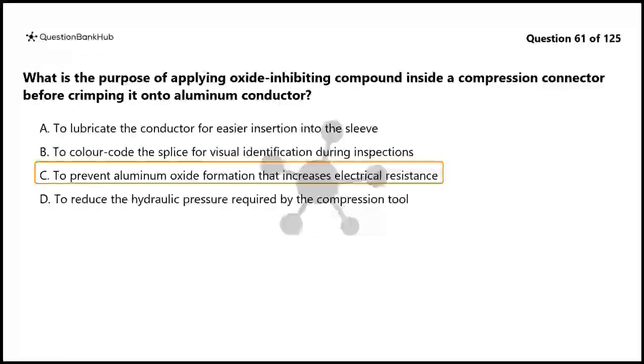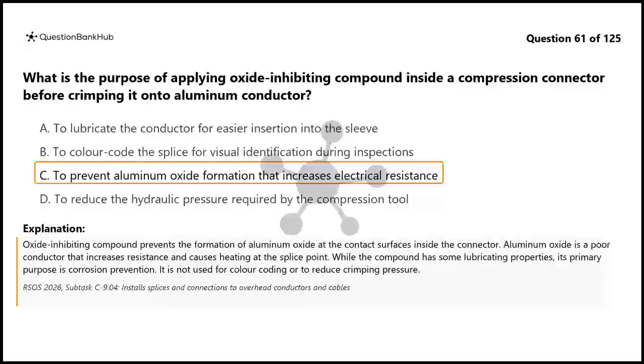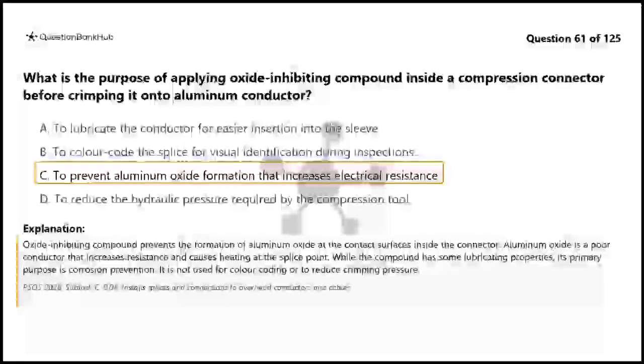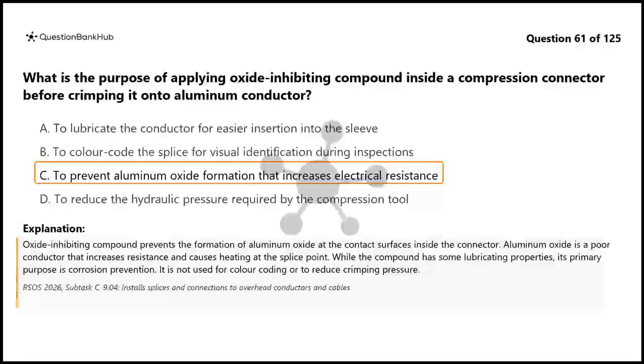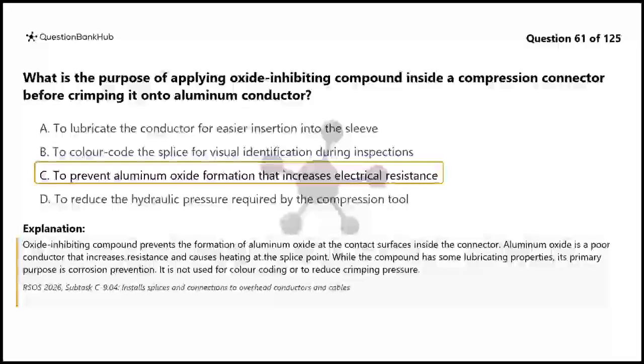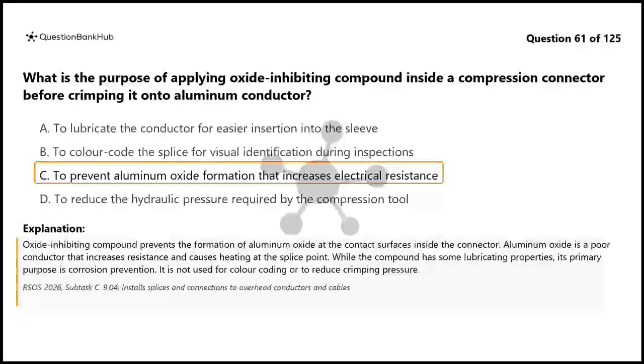The correct answer is C. Oxide-inhibiting compound prevents the formation of aluminum oxide at the contact surfaces inside the connector. Aluminum oxide is a poor conductor that increases resistance and causes heating at the splice point. While the compound has some lubricating properties, its primary purpose is corrosion prevention. It is not used for color coding or to reduce crimping pressure.